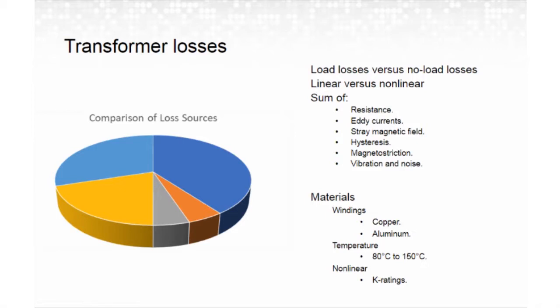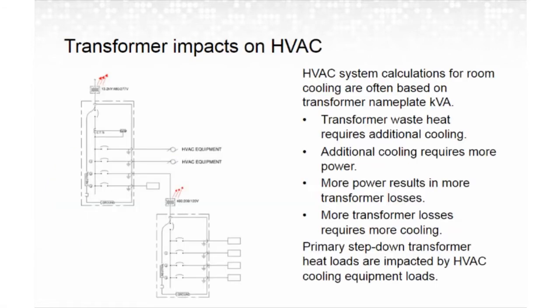Lastly, nonlinear loads can greatly increase system losses, as these load types are not addressed at all in the NEMA classification rating. Increases in harmonic content increase current and thus system losses. So due to the increase in nonlinear loads in modern buildings, it's important for designers to consider which rating is best for long-term energy savings.